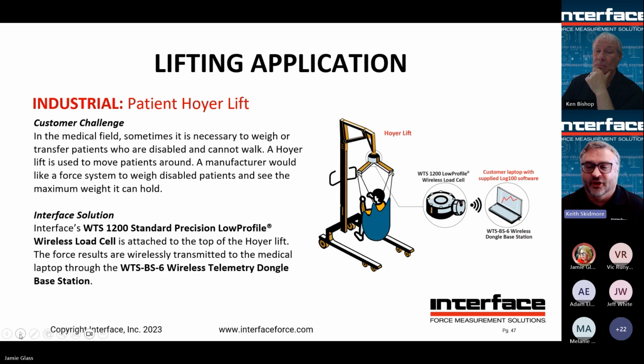Low profile load cells are good in situations where there are bending loads, so you can basically ignore those. We did have to oversize the load cell so that it wouldn't be damaged by the bending, but it's able to withstand this. They could bolt this in. Again, something like this could be moving around. You don't necessarily want wires going to it. So it's wirelessly transmitting to a PC-based logging system. Something like this, they could be moving patients on a daily basis, and they can monitor the weight from day to day to make sure they, say, aren't becoming malnourished or whatever.